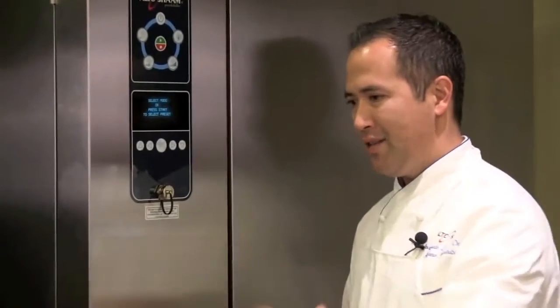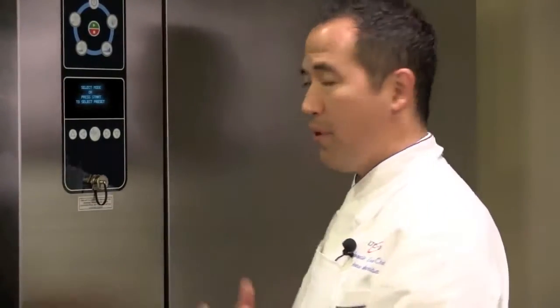In our last method, if we were running it at 24 degrees all night long, when we came back, almost certainly our product would be frozen, because it would be at a sub-freezing temperature all night. So to fix that problem, we're going to program this unit so that once the food is below 40 degrees—in this case I'll set it to 38—the chiller will rise its temperature from 24 up to 38 degrees, a refrigerator temperature, allowing the food to stay in cold storage until the next day when you can take it out and put it into your walk-in.